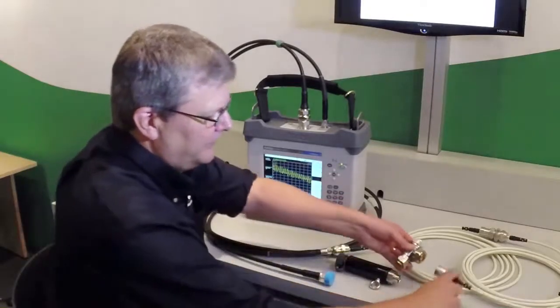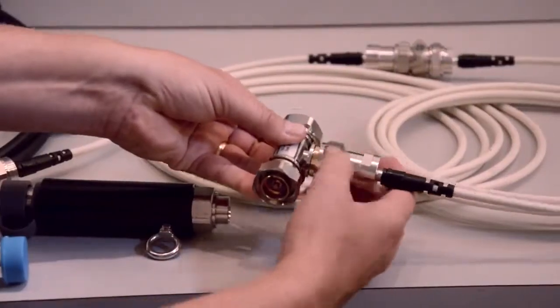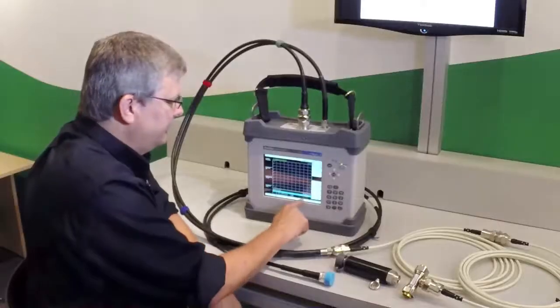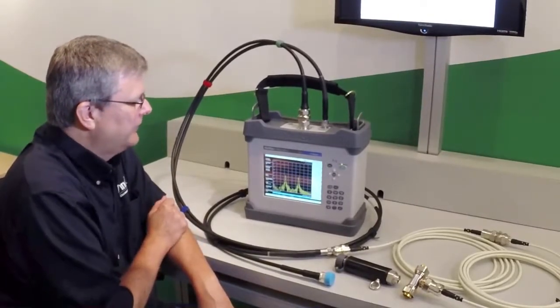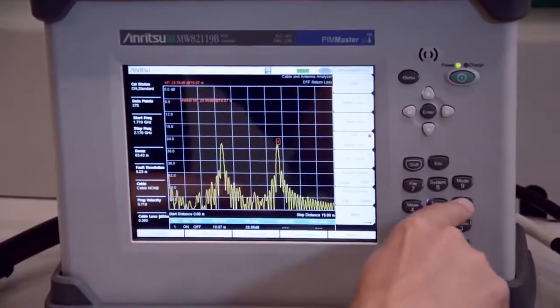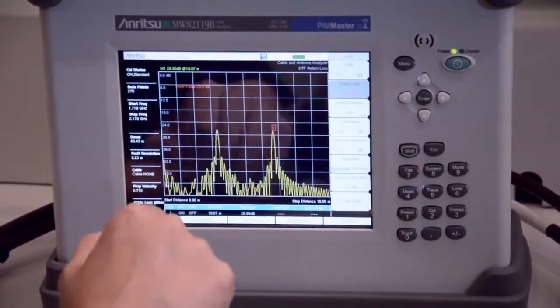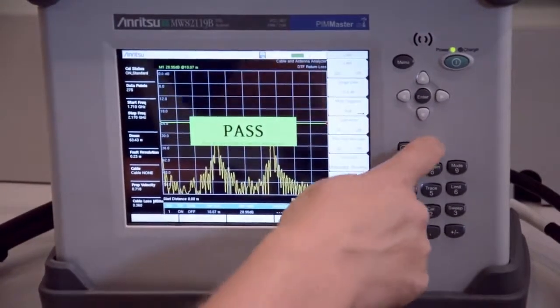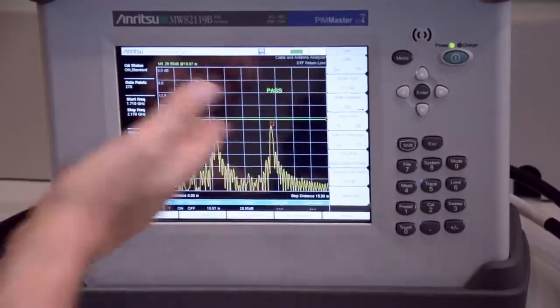The next measurement we're going to do is attaching the precision load to the end of the cable and performing a distance to fault or return loss measurement to look at the condition of the individual connectors. And in this case, we'd like to see that the individual cables are below a 25 dB level to show that each individual cable is put together correctly. And in this case, our system looks good.